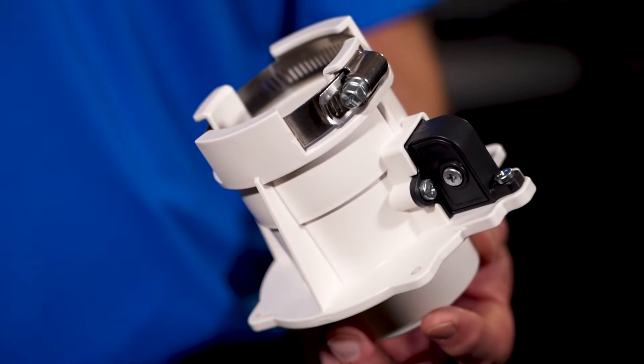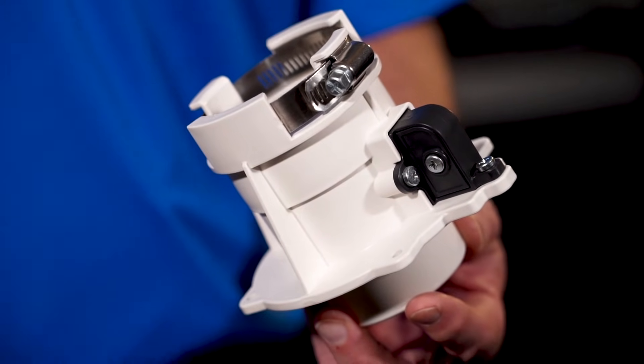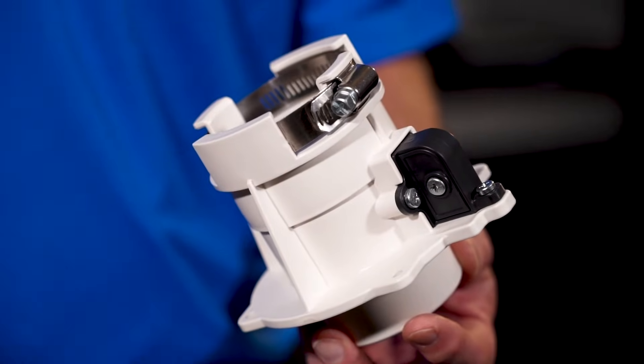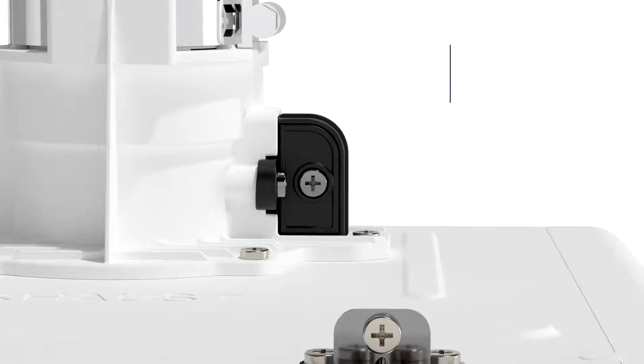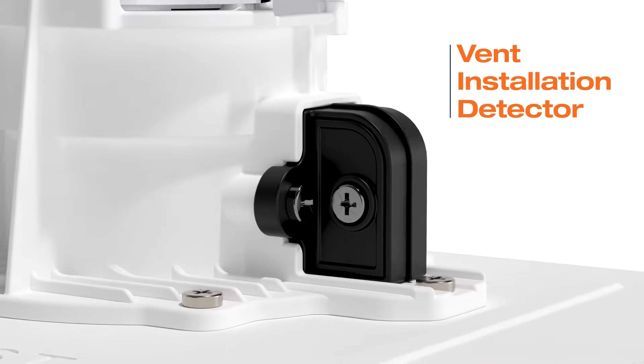One of those components is our vent installation detector, or VID. The VID is a switch that ensures that the vent pipe is fully inserted into the exhaust collar, preventing flue gases from escaping out of that connection.